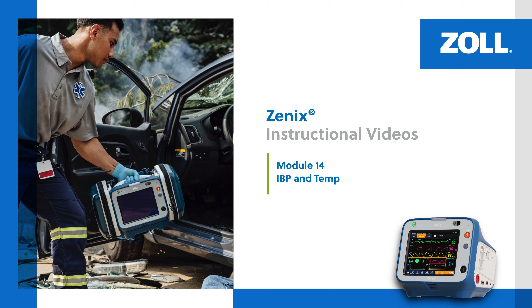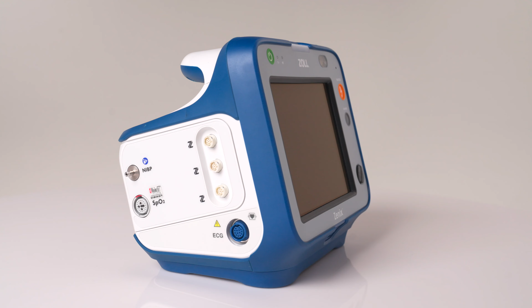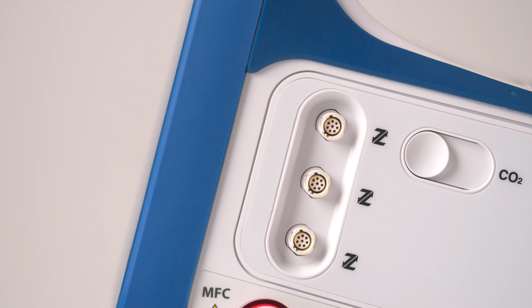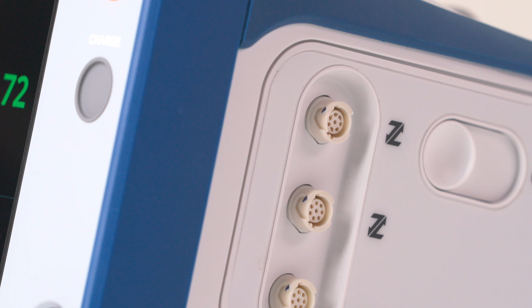In this video, we will review invasive blood pressure and temperature, which utilize the Z-Link ports on the Zenix monitor defibrillator. There are 6 Z-Link ports that can be used for monitoring invasive blood pressure or temperature. You can connect any Z-Link cable to any port. The device can monitor up to 3 invasive channels and 2 temperature channels simultaneously.